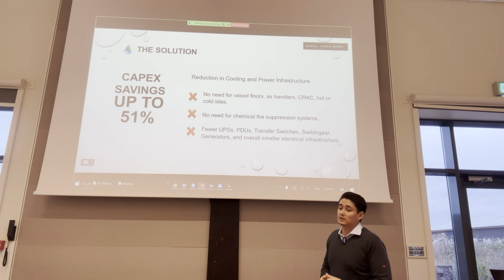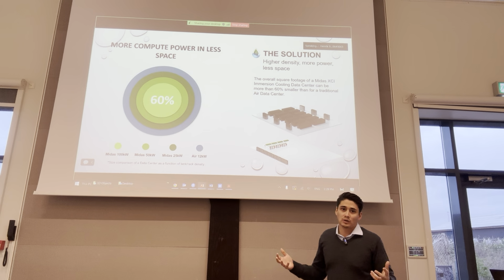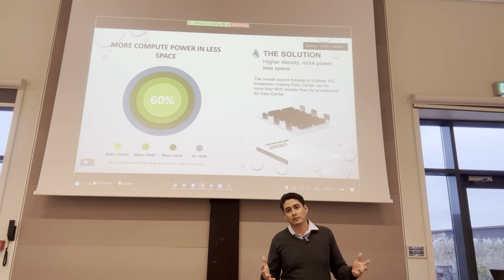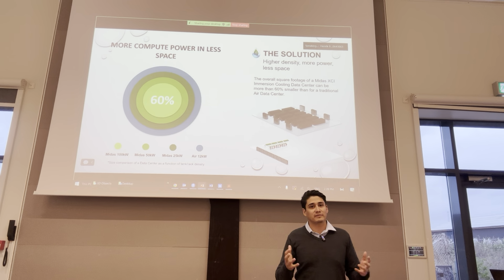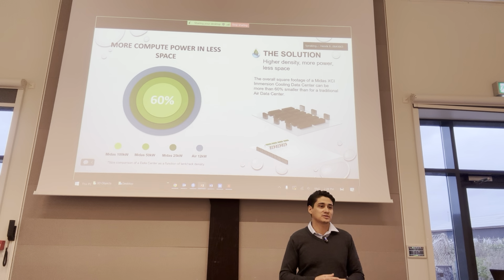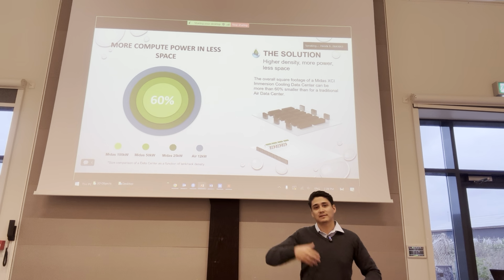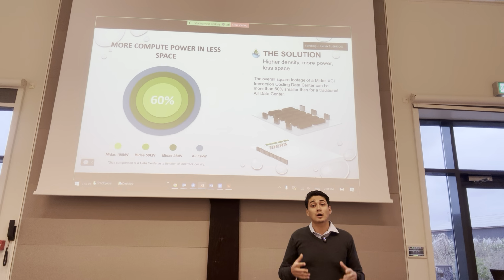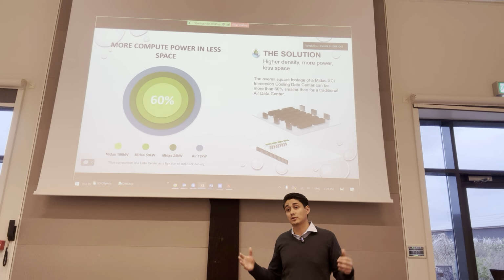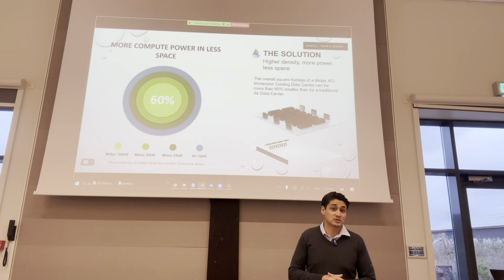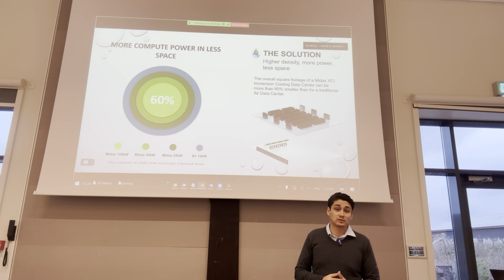And space as well. The global average is about 8 to 12 kilowatts per rack if you're generous. We're talking about 200 kilowatts in some cases, even a megawatt. We don't know exactly where we'll end up, but immersion gives you that flexibility, putting a lot of stuff into a very small area, so you can save a lot of space doing so.